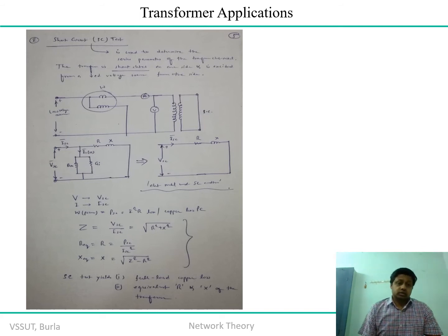When we have the short circuit combination, the flow of current is abundant, and the impact of resistance is almost zero. Therefore it is used to calculate the series parameters of the network, and in other words it is used to calculate the I square R loss, the power dissipation. Or in other words, it is also used to calculate the copper loss.